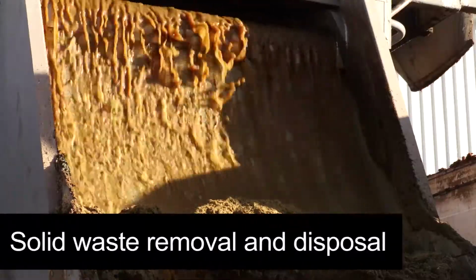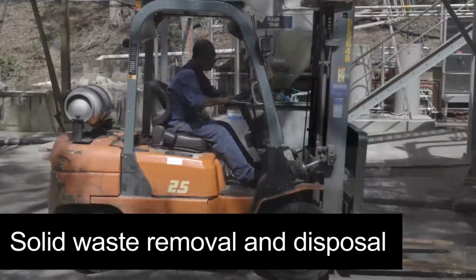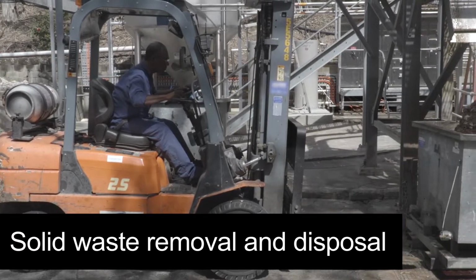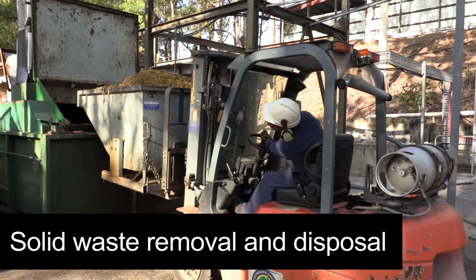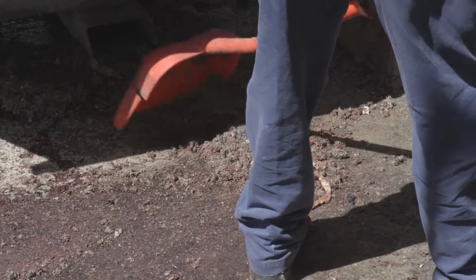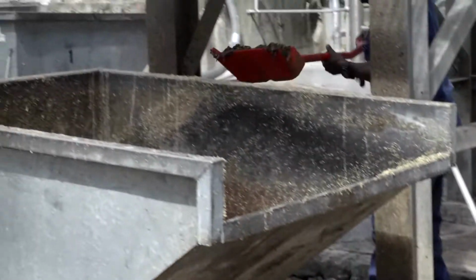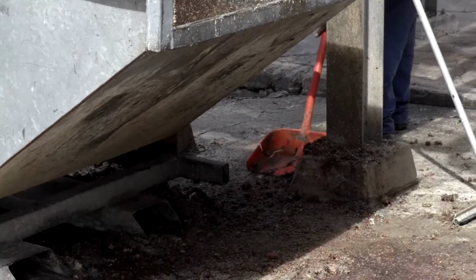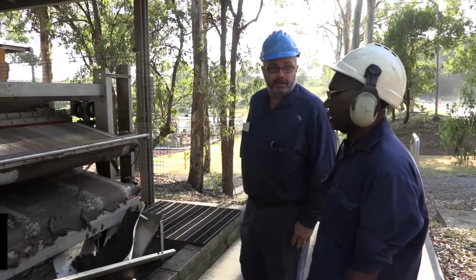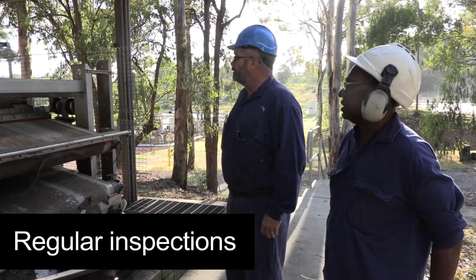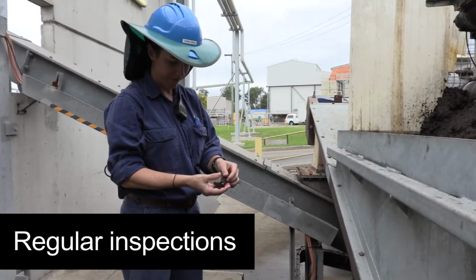Discharges are typically wet, sloppy, fatty and unpleasant to handle and may be significant in volume, up to 100 wet tonnes a week or more for a large plant. Solids should be handled carefully, since spills often return the material to the wastewater treatment system and/or sewer, which is undesirable. Inspections are usually undertaken several times a day to ensure everything is operating properly.